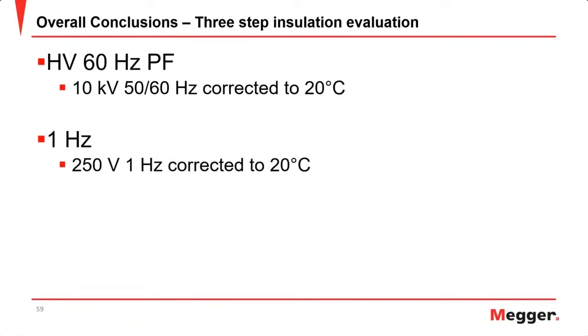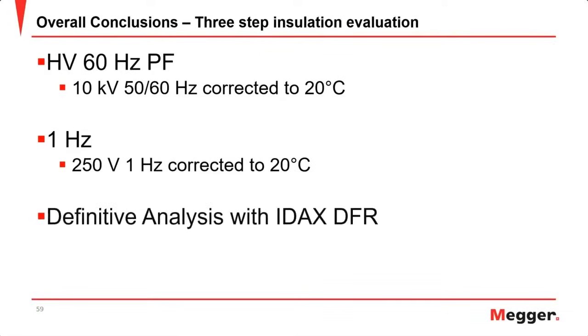And then you will correct that 1 Hertz value back to 20 degrees C using the ITC method, and that will help you determine where you may want to look for that conclusive analysis with your DFR, where you're looking from 0.1 millihertz all the way up to 1000 hertz.